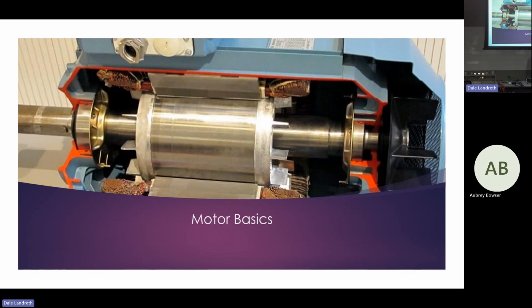I have a question on the Meg test. When you get a high number, you might get 150, 200, whatever. So why is it that a bad motor is generally reading 1 or 2 megs? I've never seen like 5 or 6 - it's generally one end or the other.